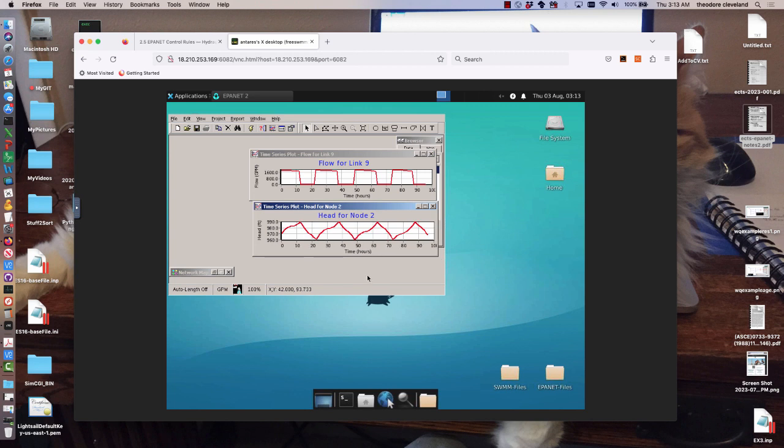Okay, before I rerun it, do you understand these two plots? The top plot is the pump on and off, and by design it's almost a square wave. That's because the pump curve is an on-off pump curve. And the bottom is the water in the tank. So we just changed it so that this upper number should go not to 990 but to 980. The lower number we left alone. Because we have less storage in the tank, we expect the pump's going to have to be on longer. But we won't know until we run the simulation.